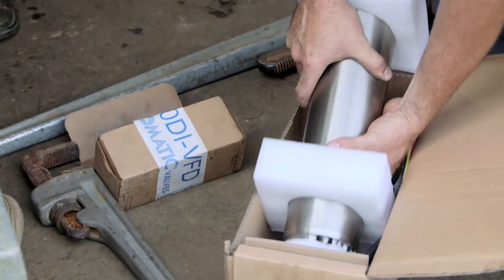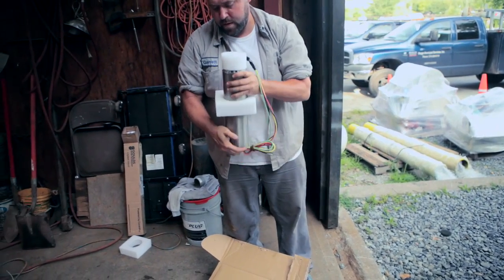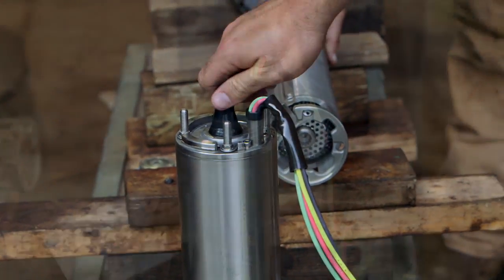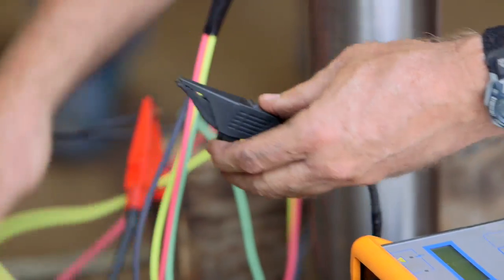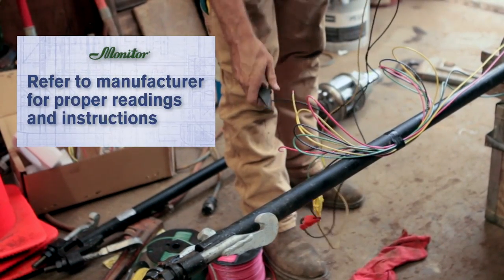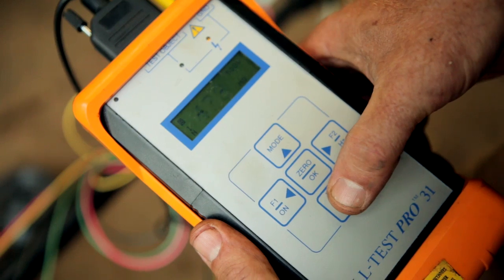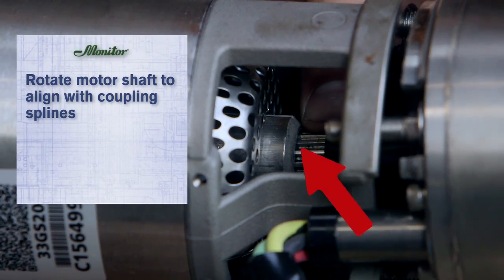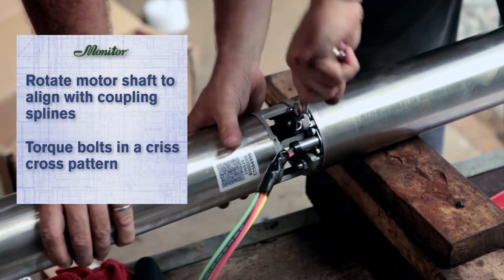Once secured to the spool assembly, the submersible motor can be installed. Before installing, inspect the motor for any damage including motor leads. Submersible motors are normally water-filled — be sure the motor is filled before operation. Complete a megohmmeter test, commonly known as a megger test, on all motor leads before installation. Refer to the manufacturer for proper readings and instructions, and always handle motor leads with care to avoid damage. If readings are acceptable, attach the submersible motor to the pump. Be sure to rotate the motor shaft to align with coupling splines, then evenly torque bolts in a criss-crossing pattern and secure in place.